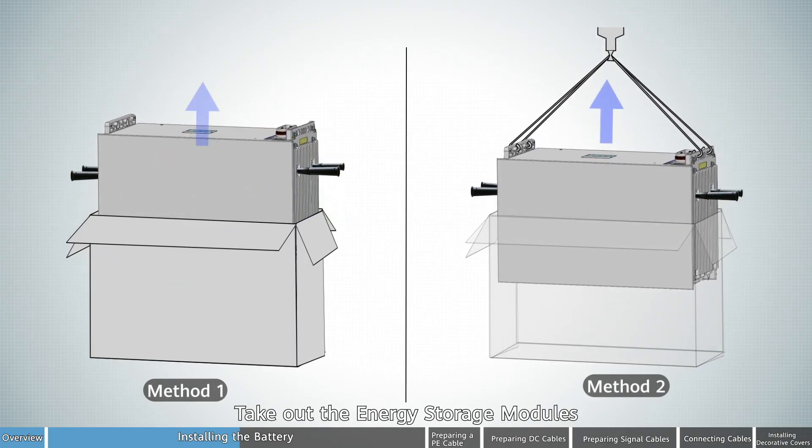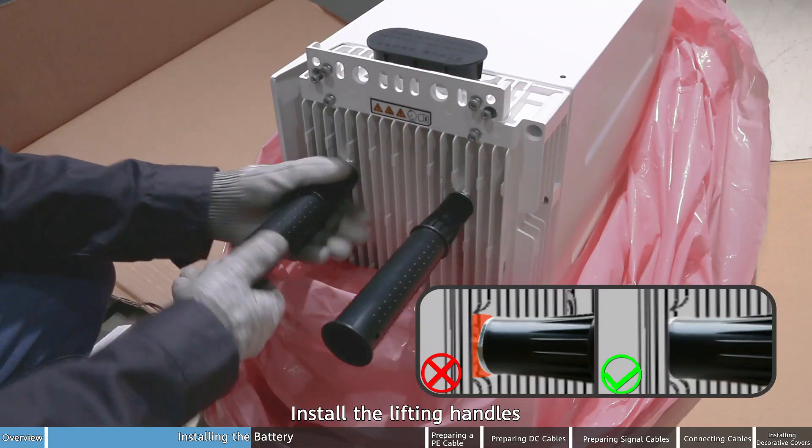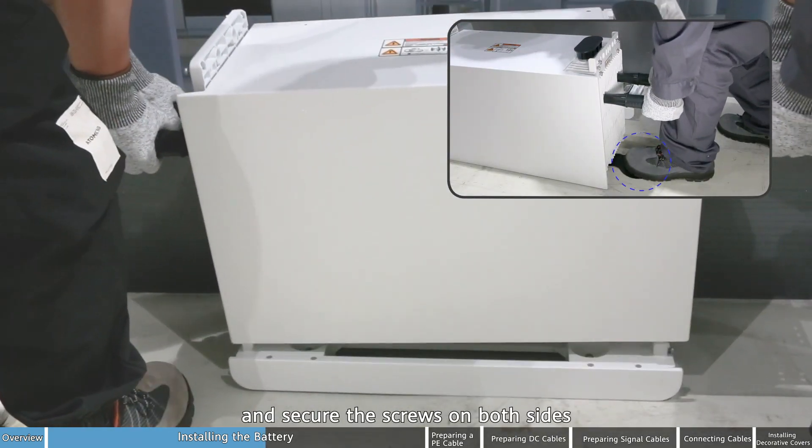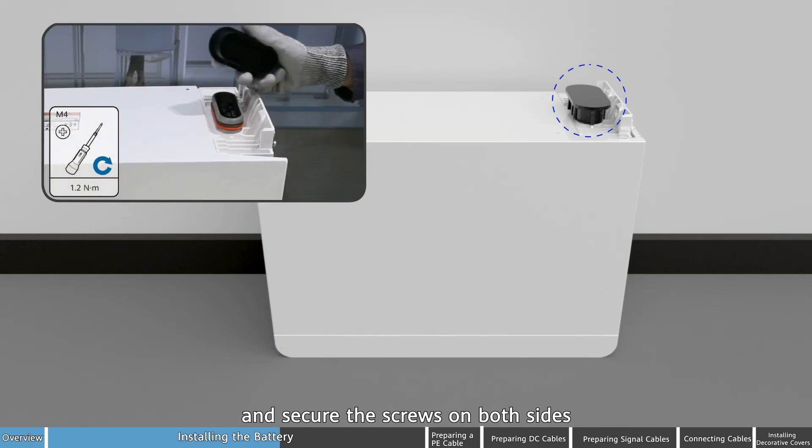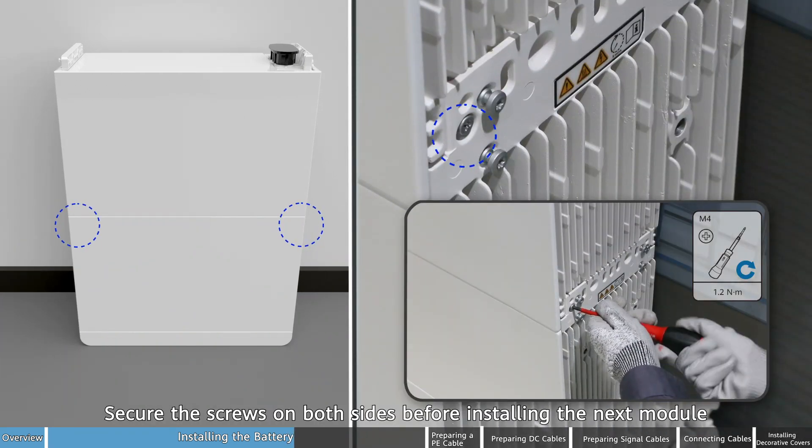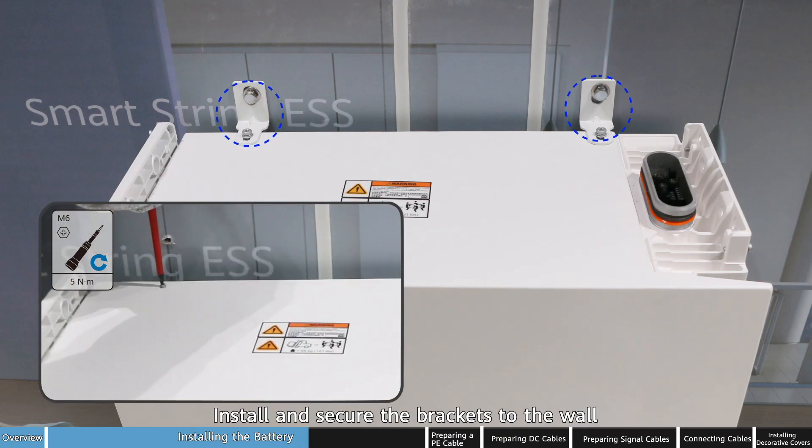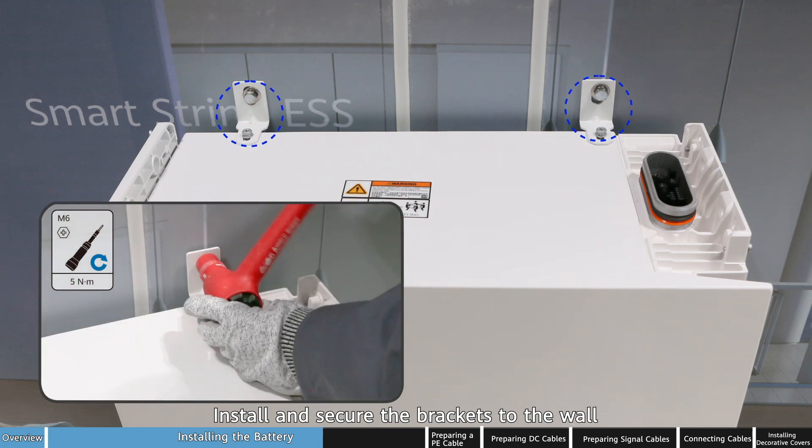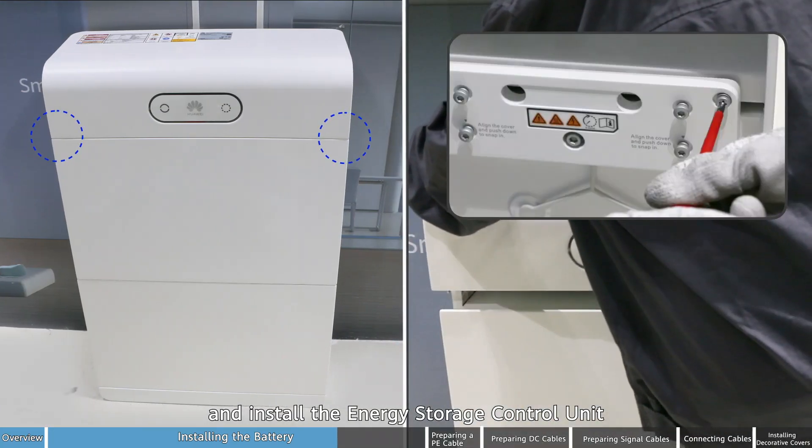Take out the energy storage modules. Install the lifting handles. Install the first energy storage module and secure the screws on both sides. Install the remaining energy storage modules in sequence. Secure the screws on both sides before installing the next module. Install and secure the brackets to the wall and install the energy storage control unit.